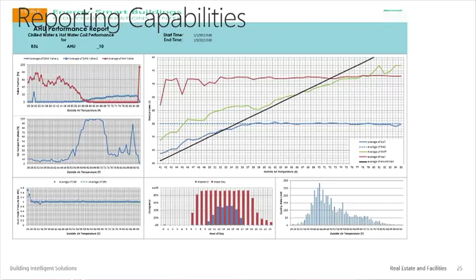So for example, if you look at, not sure what the pointer is. There's a pointer. If you look at that bell-shaped curve, that's the outside air economizer on the air handler that pulls in the fresh air. What I want to do is stay at about 10%. So it's a valve position over time. I want to stay at about 10% when it's cold, open up, pull in all that fresh air, and then close when it's hot. Well, what this one's doing is when it's 90 degrees outside, it's opening. Now I'm having to cool air.